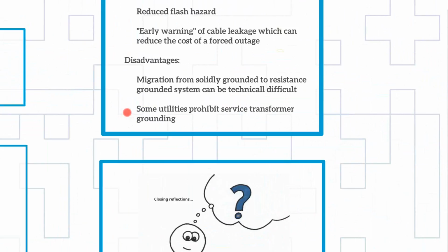And then you can get the high-speed clearing because the relay is going to look at zero sequence or the ground fault current, and it's going to trip on 40 amps instead of 4,000 amps, for example. The current will never go above 400 or 600 or whatever the design is, and the damage and everything gets dramatically less. Let's look at it from your maintenance person standpoint, Jim.